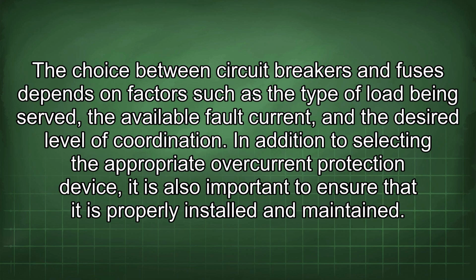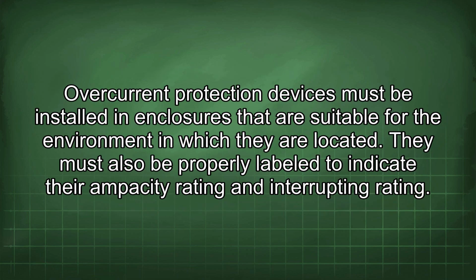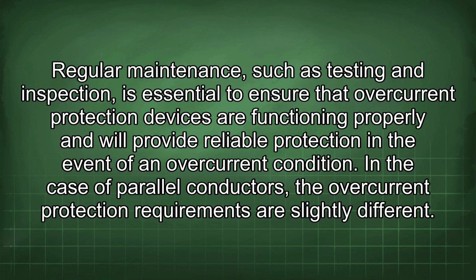In addition to selecting the appropriate overcurrent protection device, it is also important to ensure that it is properly installed and maintained. Overcurrent protection devices must be installed in enclosures that are suitable for the environment in which they are located. They must also be properly labeled to indicate their ampacity rating and interrupting rating. Regular maintenance, such as testing and inspection, is essential to ensure that overcurrent protection devices are functioning properly and will provide reliable protection in the event of an overcurrent condition.